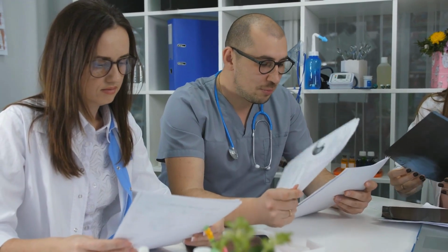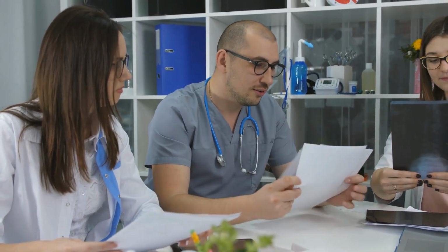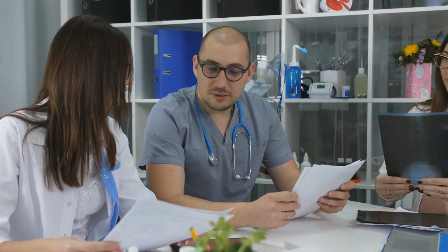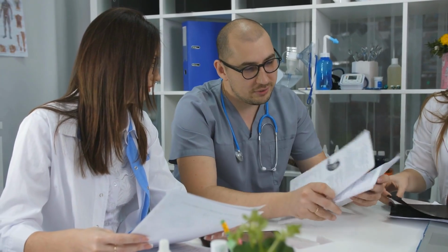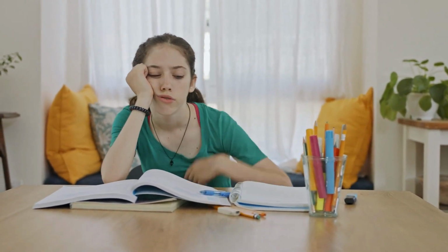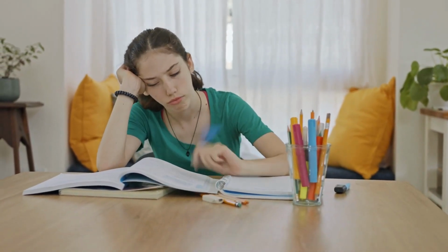Accuracy and validity. A key question many people have is, how accurate is the QbTest? Research has shown that the QbTest demonstrates good sensitivity in identifying ADHD symptoms. However, it's crucial to remember that it's not designed to be used in isolation. Its true value lies in how it complements other assessment methods. The test has been CE marked and FDA cleared, which speaks to its validity as a medical device. Like any assessment tool, its accuracy can be influenced by various factors, including the individual's state on the day of testing and how well the test instructions are followed.